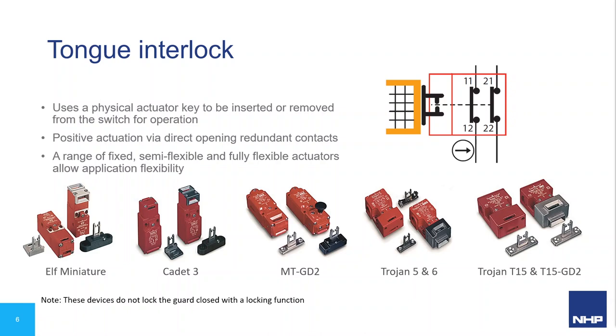The MTGD2 has strong metal construction and is versatile for most applications, using a larger industry-standard DIN or EN50041 fixing centre. These first styles have removable and rotatable heads providing eight possible actuator entry points and also offer a GD2 reinforced actuator entry slot for more demanding applications. The Trojan 5, 6, and T15 switches feature dual key entry slots and rotatable heads, offering four actuator entry options. Note: these tongue interlock devices do not lock the guard closed — they only check whether the guard is open or closed. They don't prevent the guard from opening.